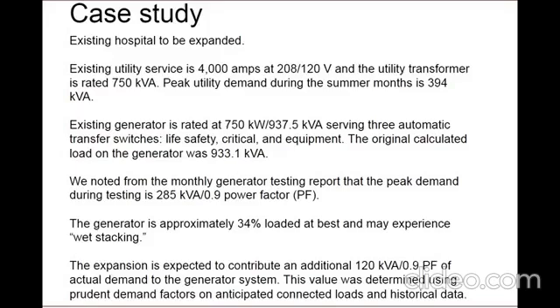When we were brought on board for the expansion, the owner and contractor expressed a concern that the original design had a very tightly loaded generator and asked if they needed to replace or add a second one for the expansion. In addition to recent utility bills, we obtained the monthly test report for the generator, which indicated a peak demand of 285 kVA at 0.9 power factor. Fluctuations in demand are expected, but this was the highest demand captured in the reports. Since generators that support a hospital do not need to be sized based on the connected loads operating simultaneously, the historical demanded values can be taken into consideration. The generator is actually oversized.